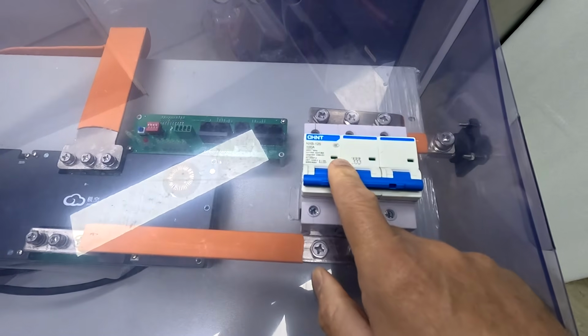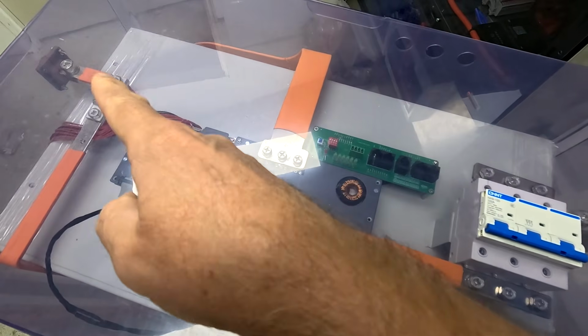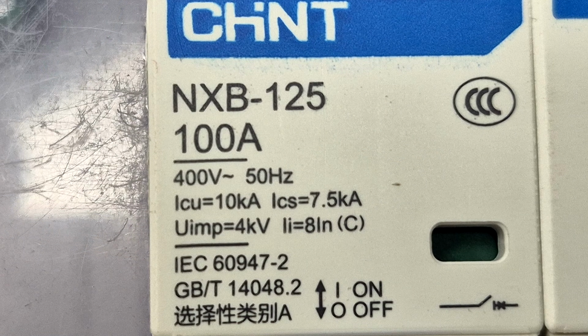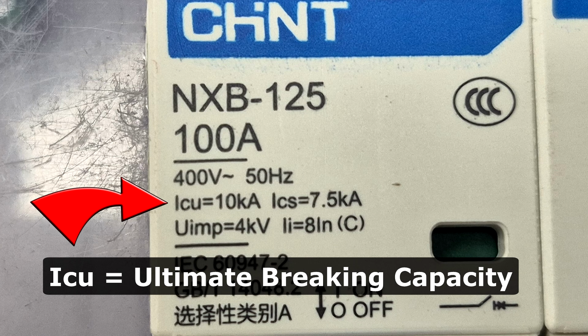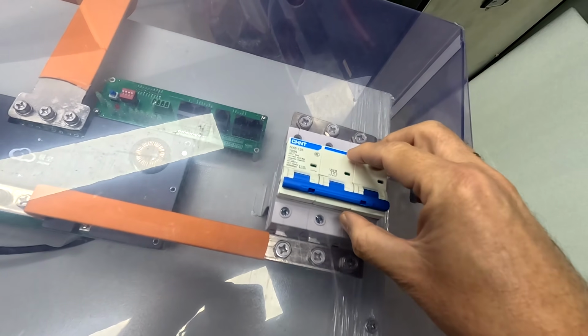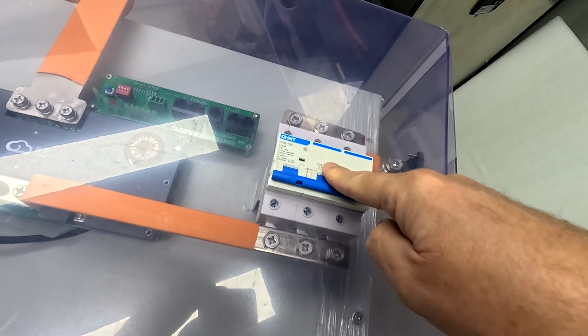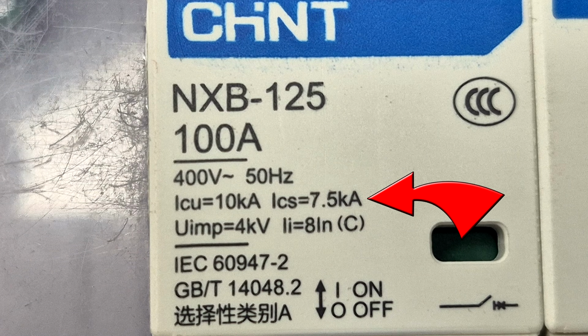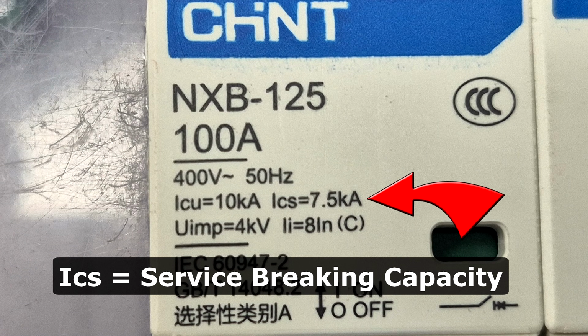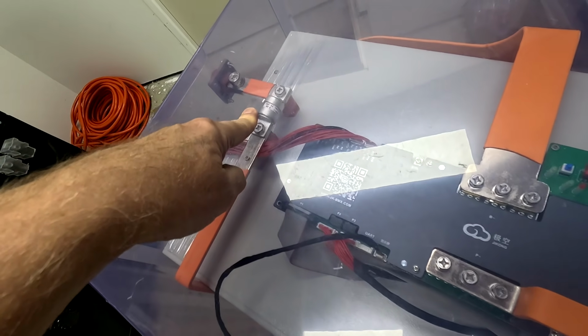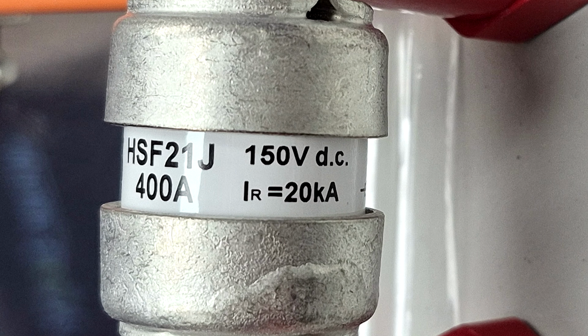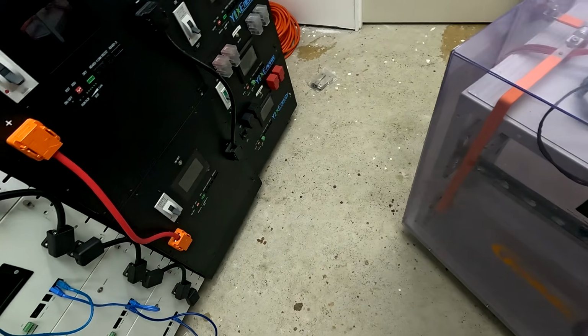And while we are talking about this, we have to talk about this breaker and the fuse as well. This one has an ICU of 10 kiloamps here, but the ICU is the ultimate breaking capacity. This only tells us that the breaker can disconnect 10 kiloamps without exploding. Usually the breaker needs to be replaced after that. And the ICS, the service breaking capacity, is only 7.5 kiloamps. So it can safely disconnect 7.5 kiloamps and can be reused afterwards. Obviously the fuse has only one parameter, because when it's blown, it's gone.